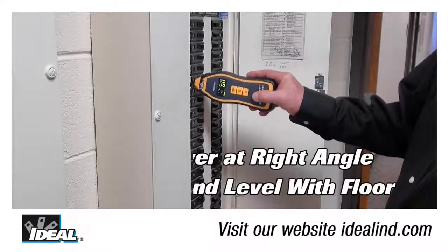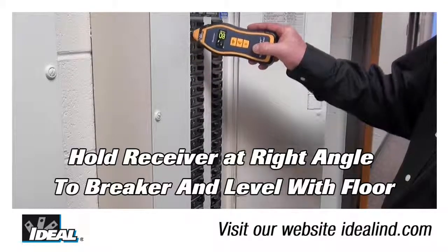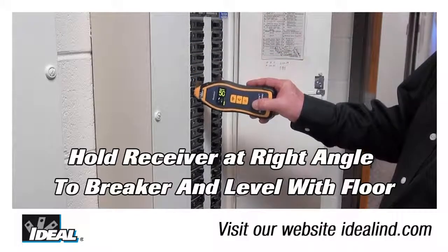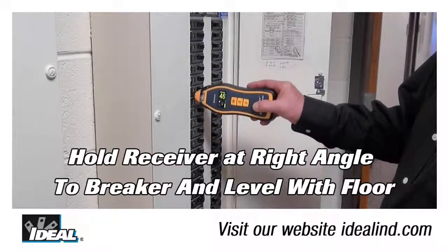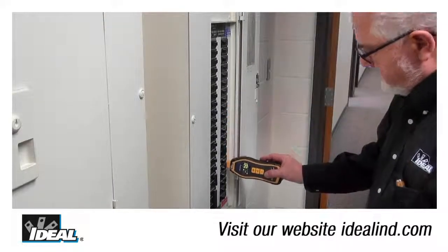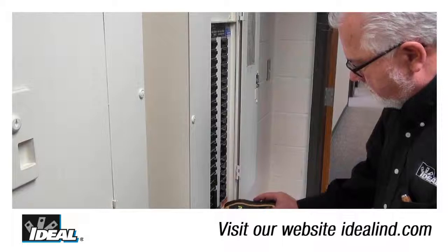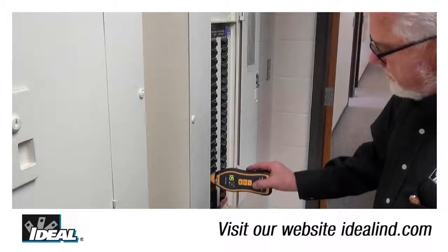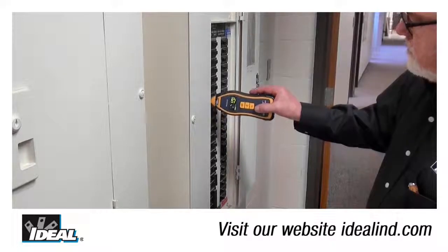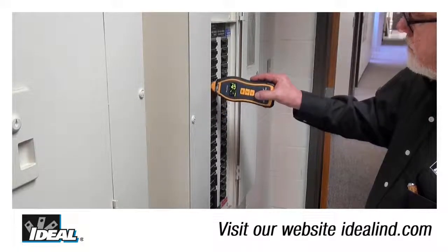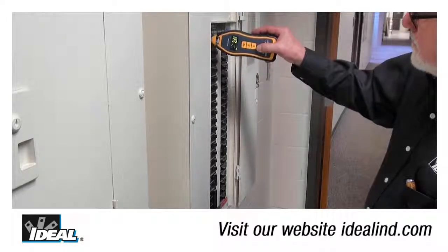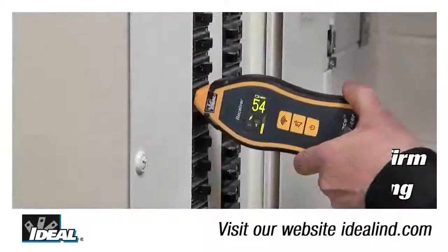Starting in the upper left or right corner of the panel, hold the nose of the receiver at right angles to the breaker over the location where the branch circuit conductor is located to the breaker. Scan around in a consistent manner, keeping the orientation of the receiver the same for the entire scan, and be sure to go around the breakers completely once, noting the area where you obtained the highest reading. Be sure that all the breakers in the panel have been scanned, and on the second scan, confirm your observations and determine the breaker with the highest reading.